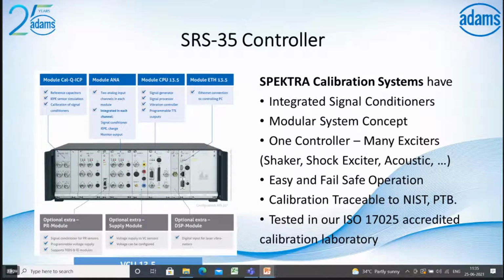It has communication options: you can connect either through Ethernet or through RS-232. It also has a piezoresistive module for calibrating piezoresistive sensors. It has optional power supply modules for giving the excitation power supply for DC sensors. And for the primary calibration, for the laser input, it has a different module. That's optional, along with the primary calibration systems. It is traceable to the National Institute of Standards and Technology and the German PTB standards, and tested in ISO 17025 accredited calibration laboratories.